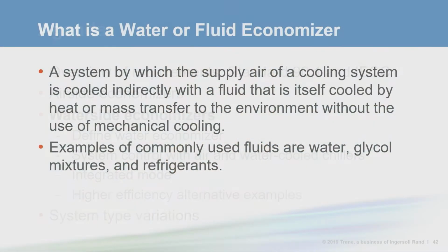So what is a water or waterside economizer? This is the definition that ASHRAE uses. A system by which the supply air of a cooling system is cooled indirectly with a fluid that is itself cooled by heat or mass transfer to the environment without the use of mechanical cooling.